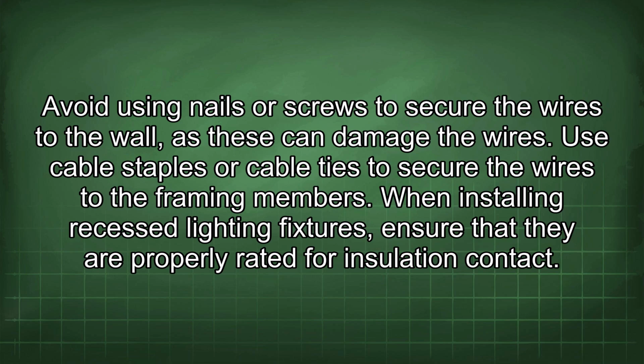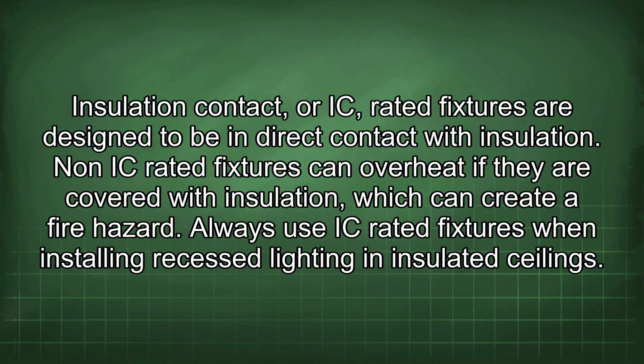When installing recessed lighting fixtures, ensure that they are properly rated for insulation contact. Insulation contact, or IC, rated fixtures are designed to be in direct contact with insulation. Non-IC rated fixtures can overheat if they are covered with insulation, which can create a fire hazard. Always use IC rated fixtures when installing recessed lighting in insulated ceilings.